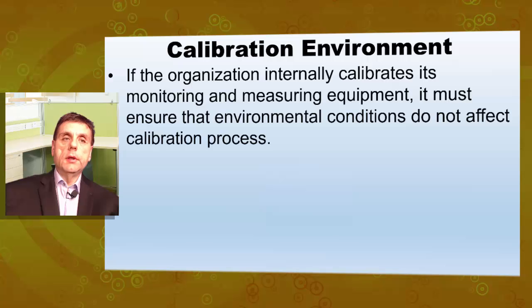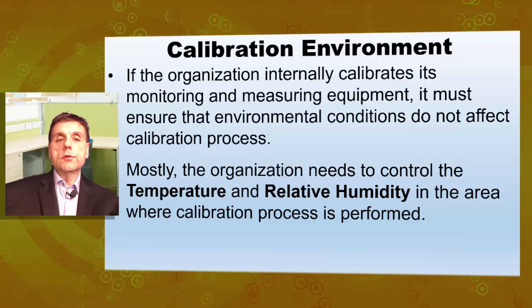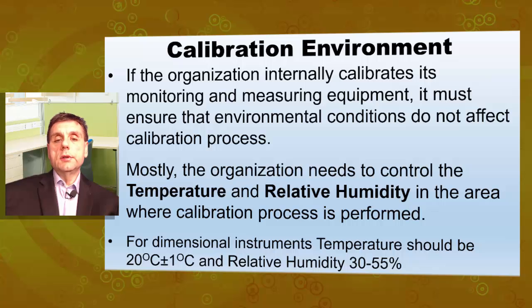Calibration environment. If the organization internally calibrates its monitoring and measuring equipment, it must ensure that environmental conditions do not affect the calibration process. Mostly, the organization needs to control the temperature and relative humidity in the area where a calibration process is performed. For dimensional instruments like micrometers, verniers, height gauges, and so on, temperature should be 20 degrees Celsius plus minus 1 degree Celsius, and relative humidity between 30 and 55%.